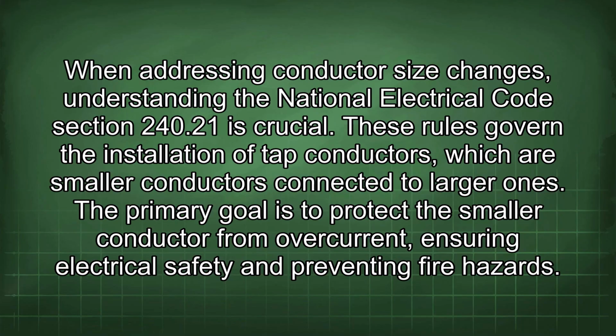When addressing conductor size changes, understanding the National Electrical Code Section 240.21 is crucial. These rules govern the installation of tap conductors, which are smaller conductors connected to larger ones. The primary goal is to protect the smaller conductor from overcurrent, ensuring electrical safety and preventing fire hazards.